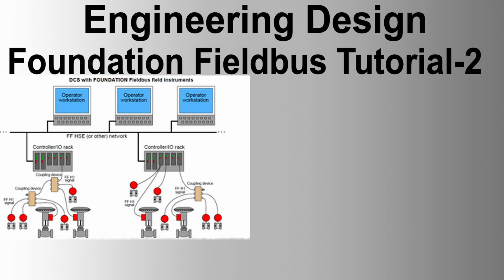Parameters. A block has a series of parameters that are accessible by choosing one with an FMS index. Parameters of a block have continuous indices. Parameter classes. Output parameters: an output of a function block that can be connected to input parameters of other function blocks. Input parameters: an input of a function block that can accept one output parameter of another function block. Contained parameters: neither input nor output, accessible only through on-demand read or write request.